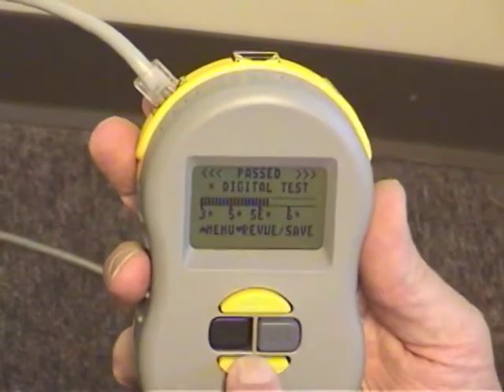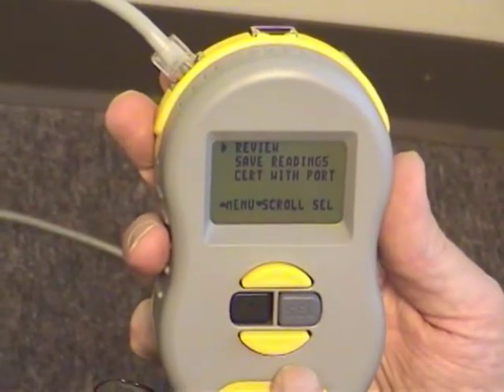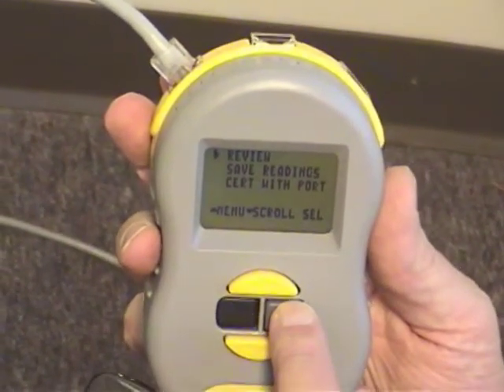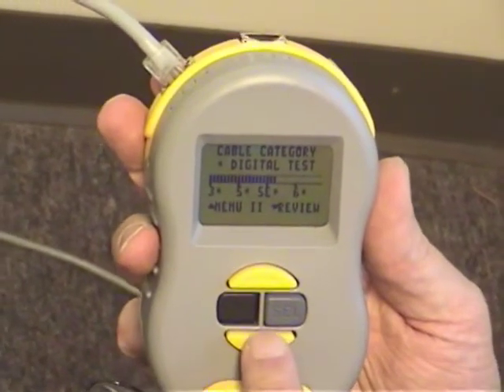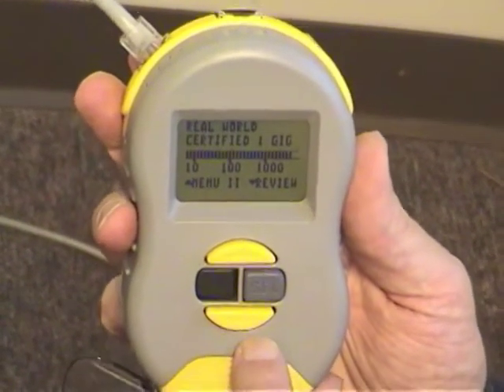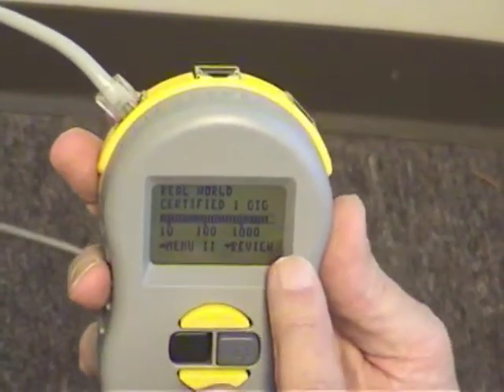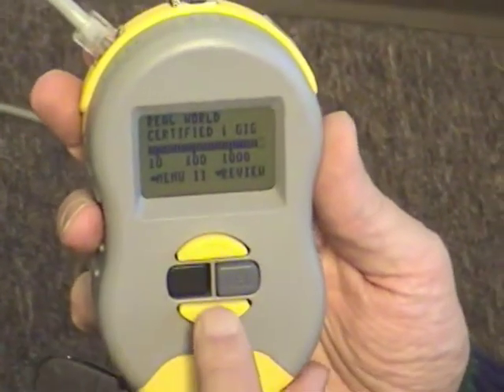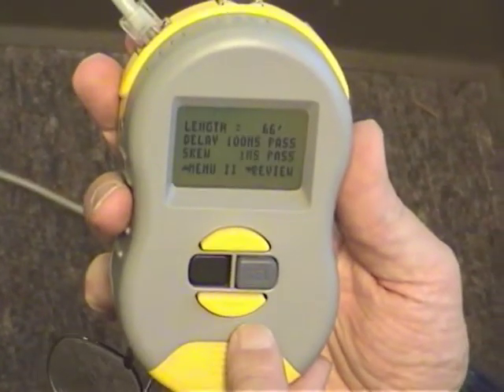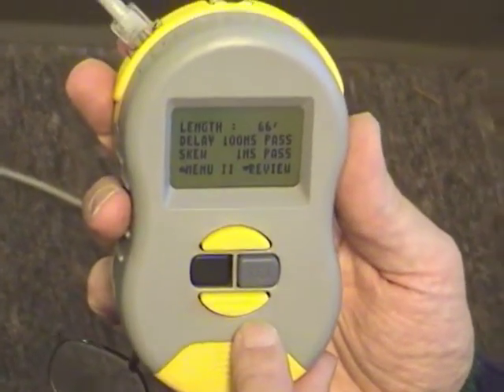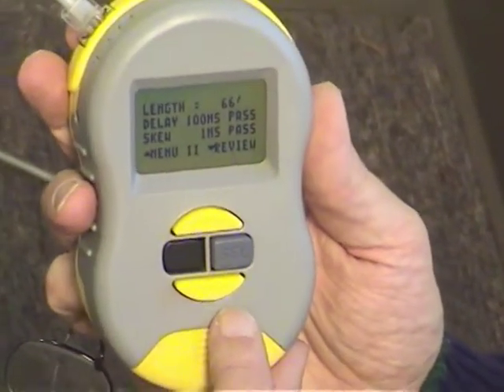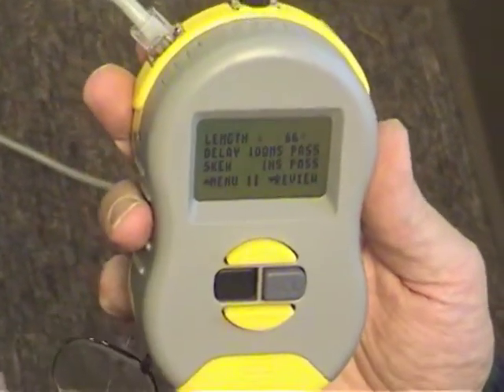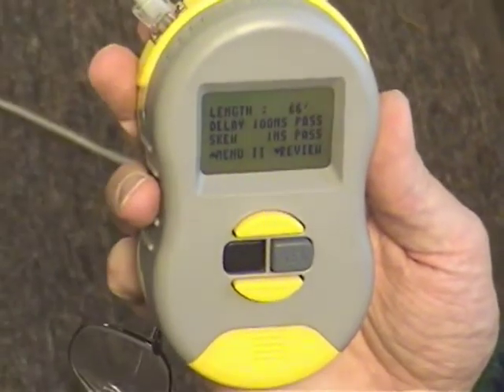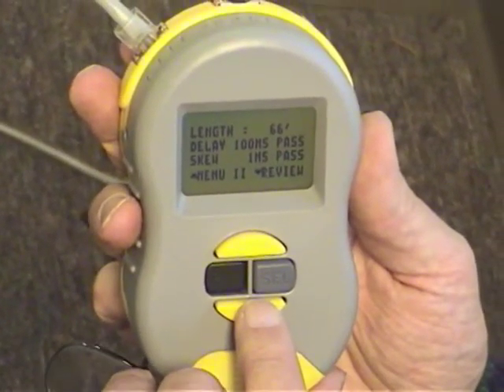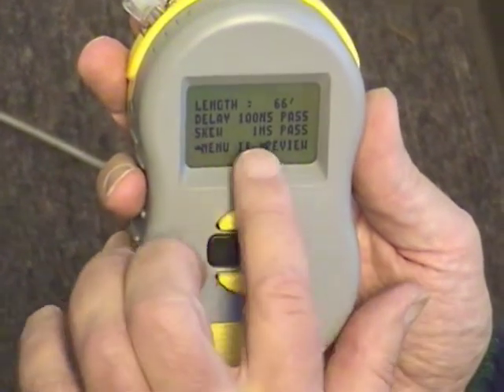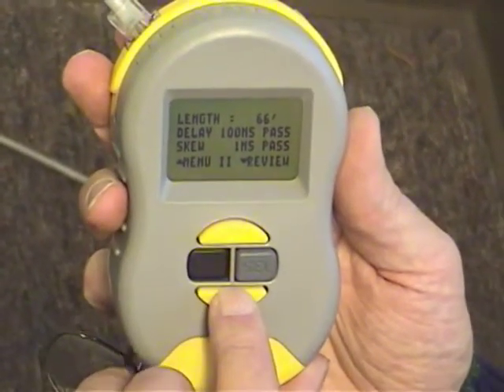Now we go down to review the readings and see what we have here. It tells us this cable is capable of carrying a gig, so we don't have to replace this one. It tells us the cable is 66 feet long, and the delay - the time it takes for data to go from one end of the cable to the other - is only 100 nanoseconds. The skew between pairs is only 1 nanosecond, so it's a pretty good cable.